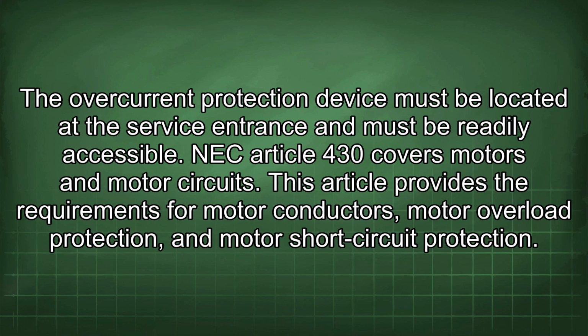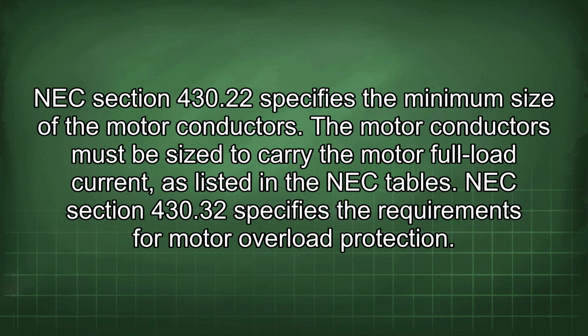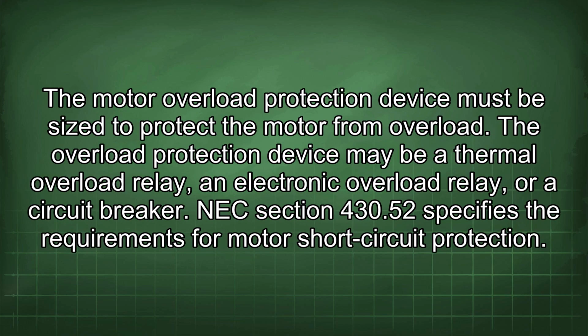NEC Article 430 covers motors and motor circuits. This article provides the requirements for motor conductors, motor overload protection, and motor short circuit protection. NEC Section 430.22 specifies the minimum size of the motor conductors. The motor conductors must be sized to carry the motor full load current as listed in the NEC tables. NEC Section 430.32 specifies the requirements for motor overload protection. The motor overload protection device must be sized to protect the motor from overload. The overload protection device may be a thermal overload relay, an electronic overload relay, or a circuit breaker.